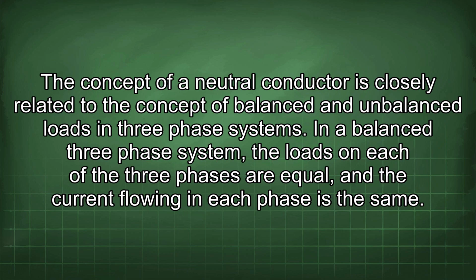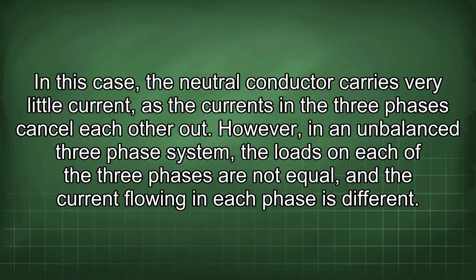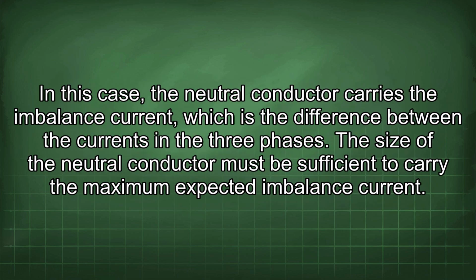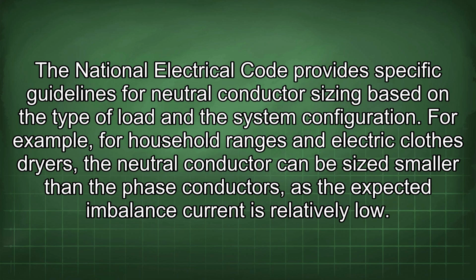The concept of a neutral conductor is closely related to the concept of balanced and unbalanced loads in three-phase systems. In a balanced three-phase system, the loads on each of the three phases are equal, and the current flowing in each phase is the same. In this case, the neutral conductor carries very little current, as the currents in the three phases cancel each other out. However, in an unbalanced three-phase system, the loads on each of the three phases are not equal, and the current flowing in each phase is different. In this case, the neutral conductor carries the imbalanced current, which is the difference between the currents in the three phases. The size of the neutral conductor must be sufficient to carry the maximum expected imbalanced current. The National Electrical Code provides specific guidelines for neutral conductor sizing based on the type of load and the system configuration.